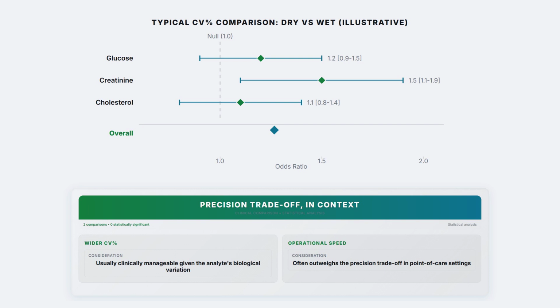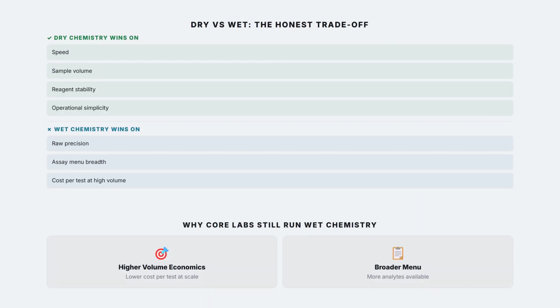Weighed as a genuine trade-off rather than a marketing pitch, dry chemistry wins decisively on speed, sample volume, reagent stability, and operational simplicity. Wet chemistry generally wins on raw precision, assay menu breadth, and cost per test at high volume, which is exactly why most large core laboratories still run wet chemistry platforms as their primary workhorse.